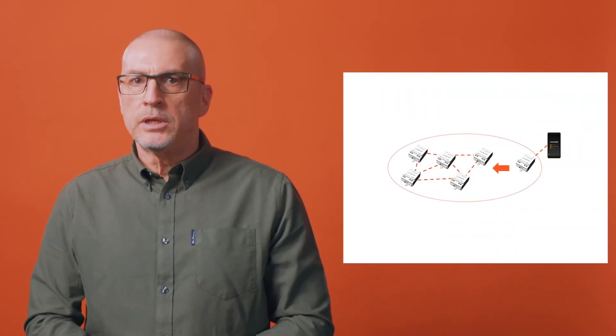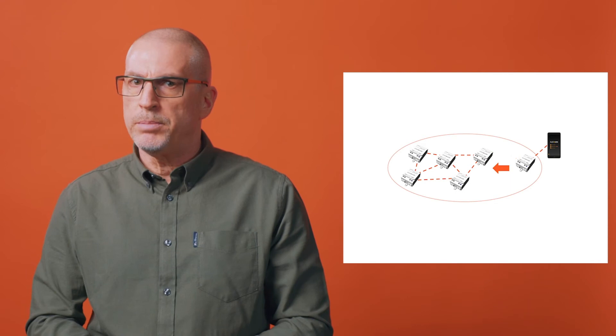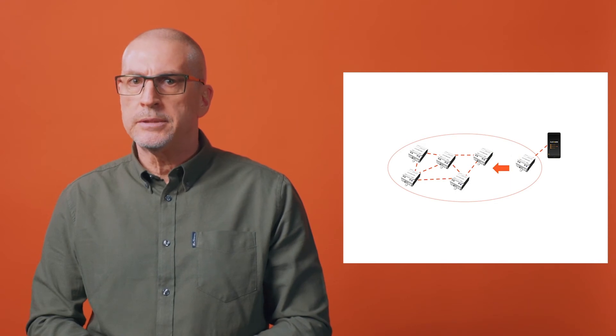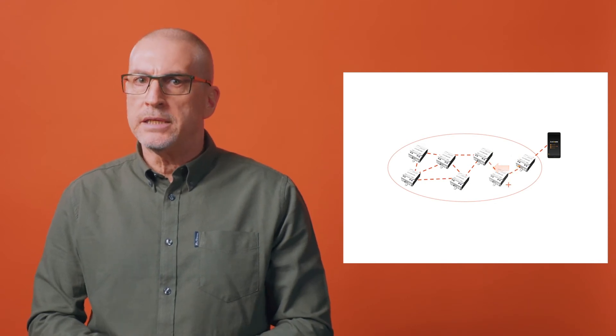There are two ways to solve an island issue. Either move devices closer together, which is not usually possible or desired, or add another Casambi device to the network to create a communication bridge. The additional device only needs to be paired to the network. It doesn't need to be programmed to do anything.